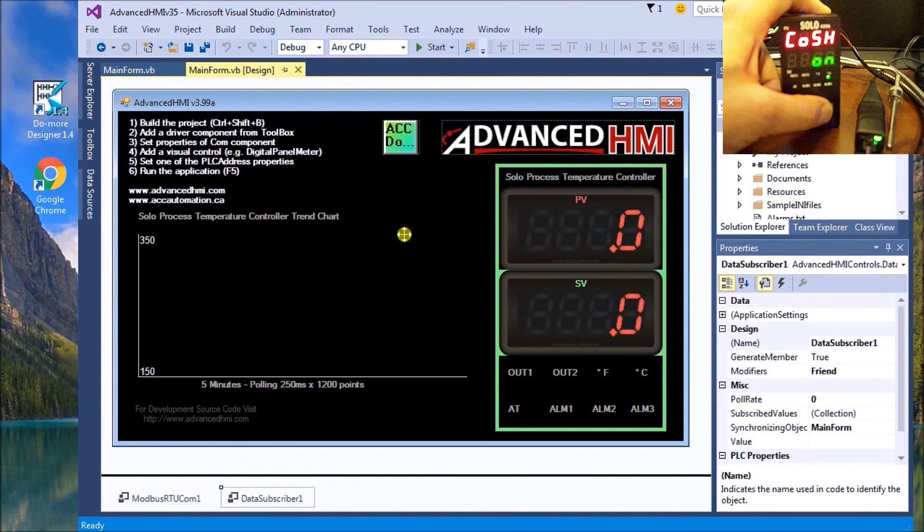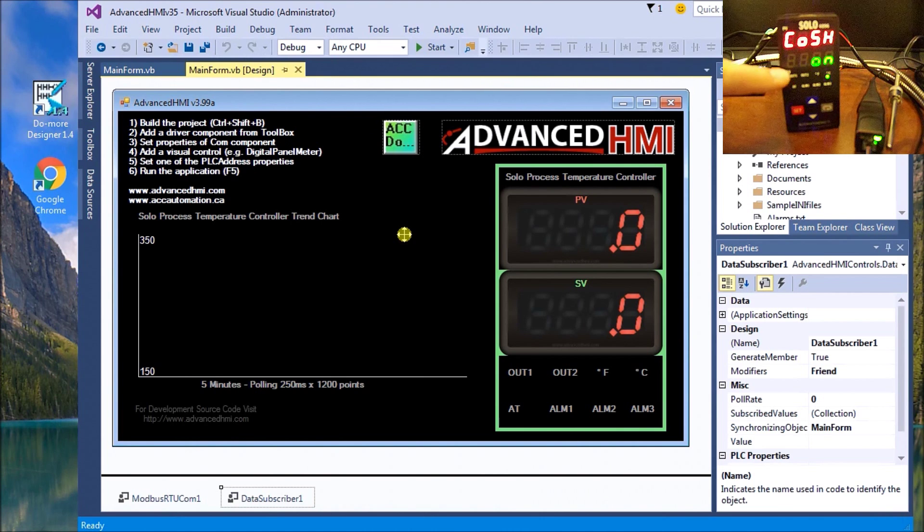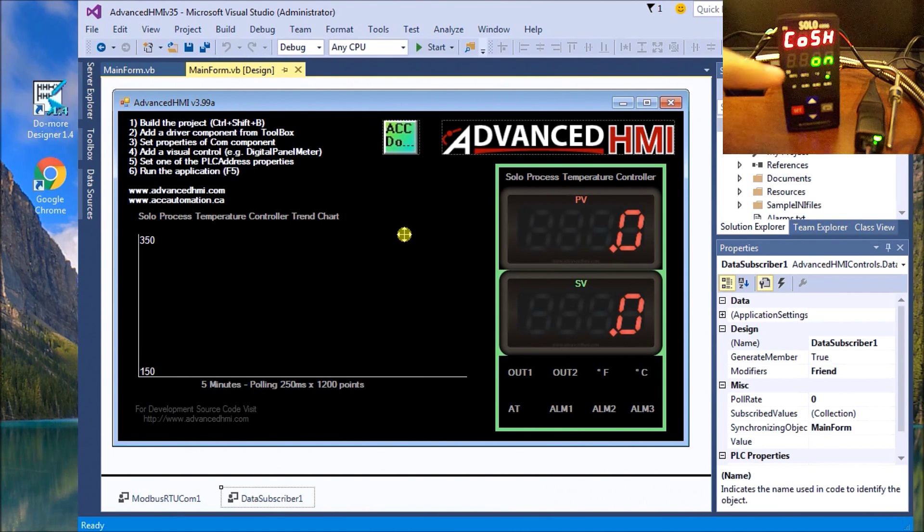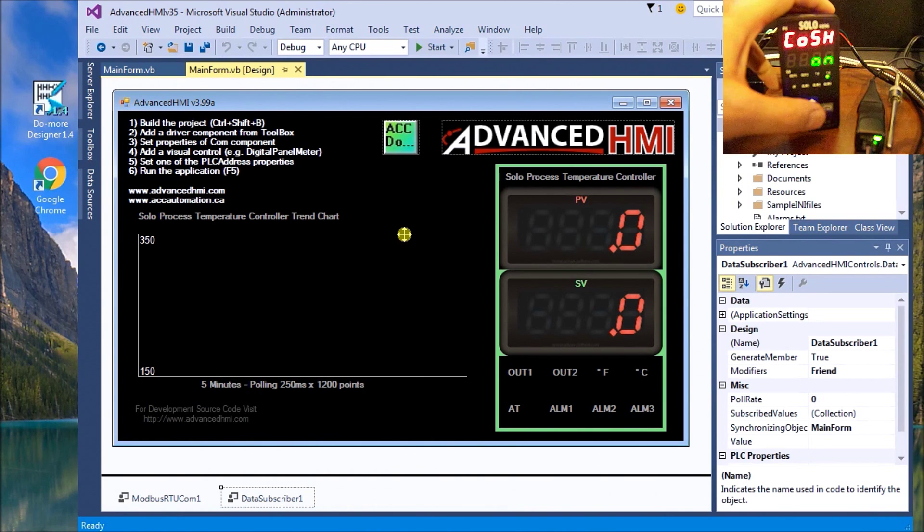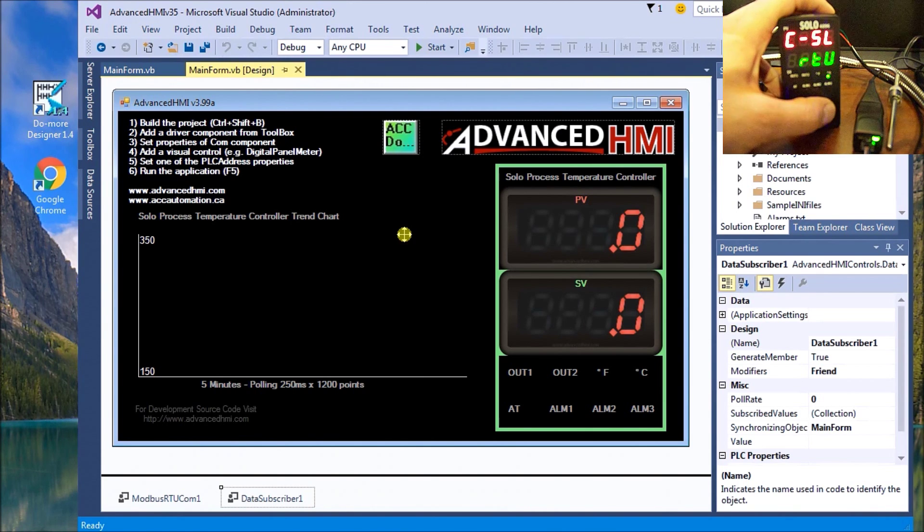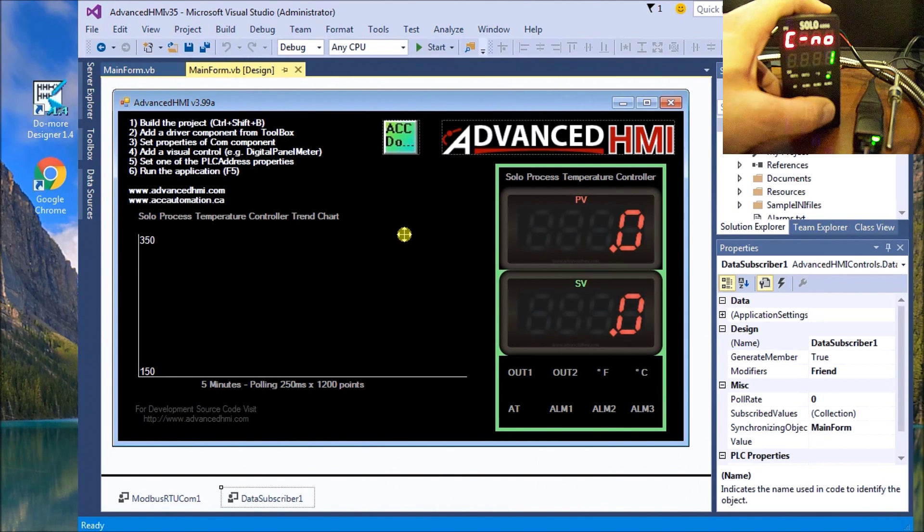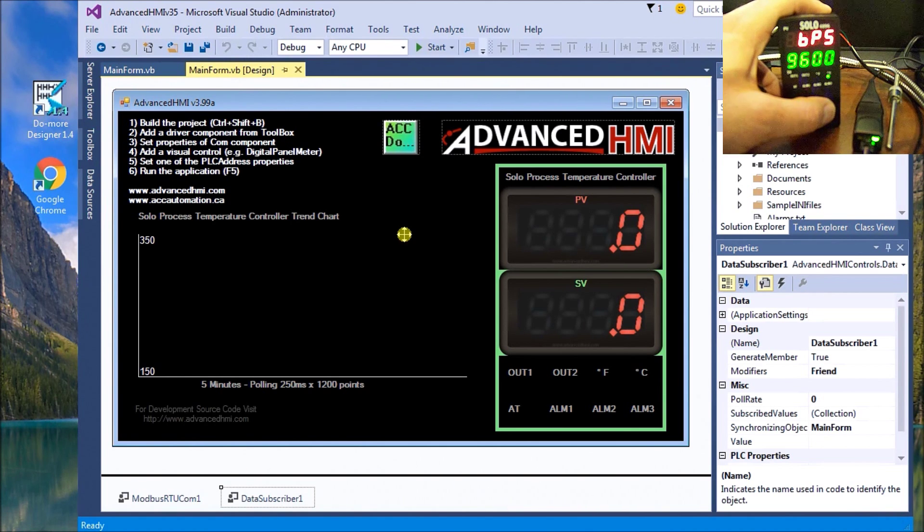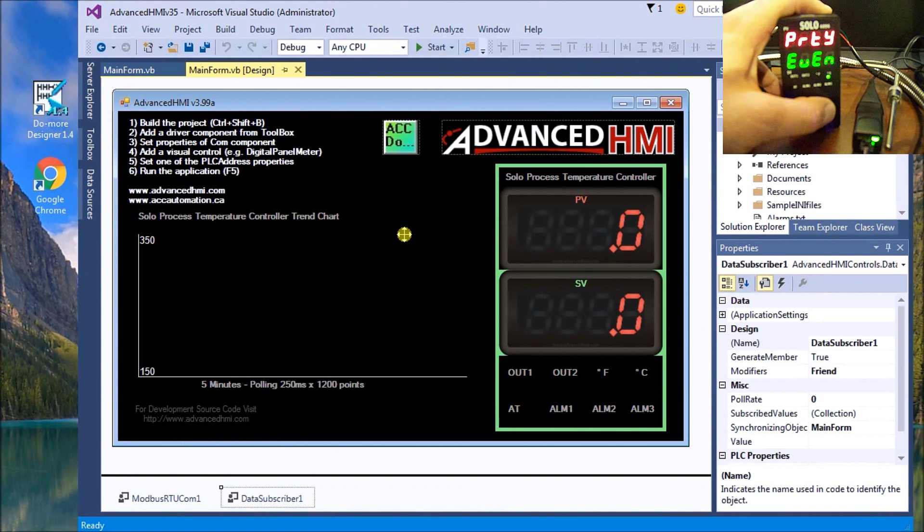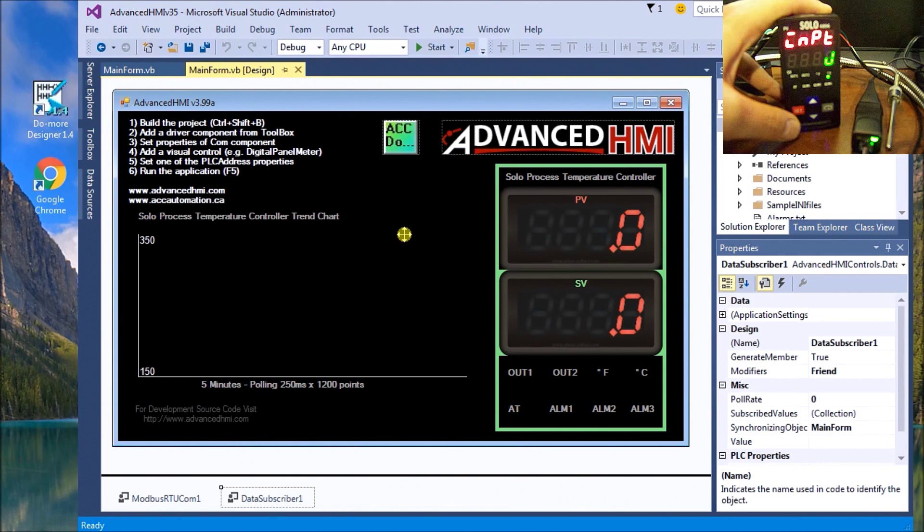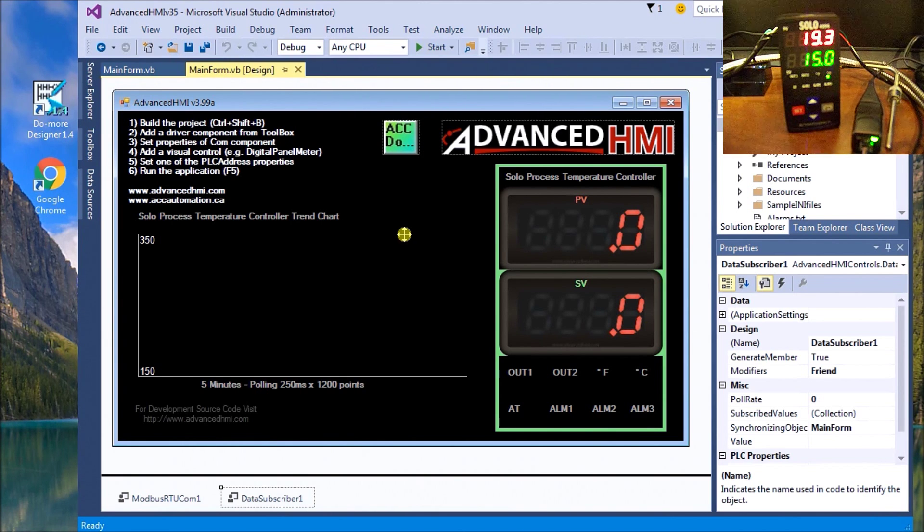This setting here tells us that we're going to be using online communication or activate that RS-485 port on the back. The next setting is we're using protocol RTU on Modbus, unit number one, and baud rate 9600, eight bits, even parity, one stop bit. We hit back set and we're back to run mode again.